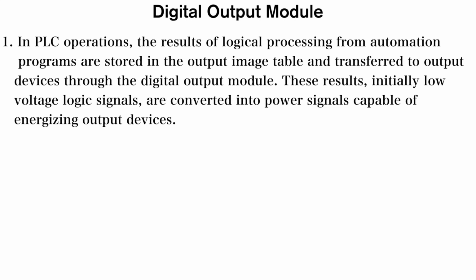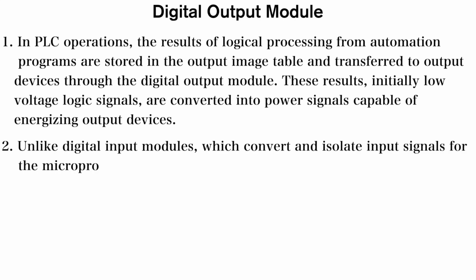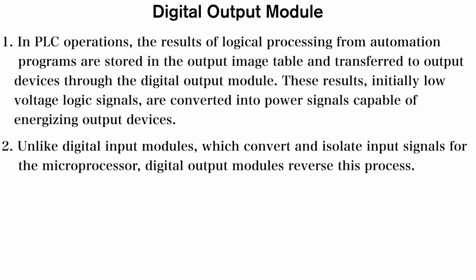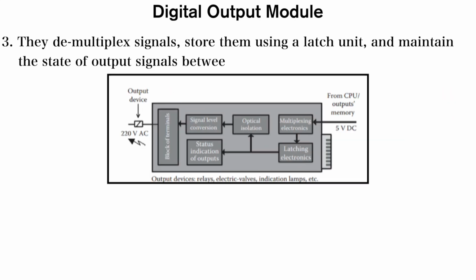The output module results are initially low voltage logic signals and are converted into power signals, which are capable of energizing the output devices or powering up the output devices for indication. Unlike the digital input modules, which convert and isolate the input signal for the microprocessor, the digital output modules reverse this process. Basically, digital output modules demultiplex the signals and store them using a latch unit, maintaining the state of the output signal between the various scans to ensure consistent operation.